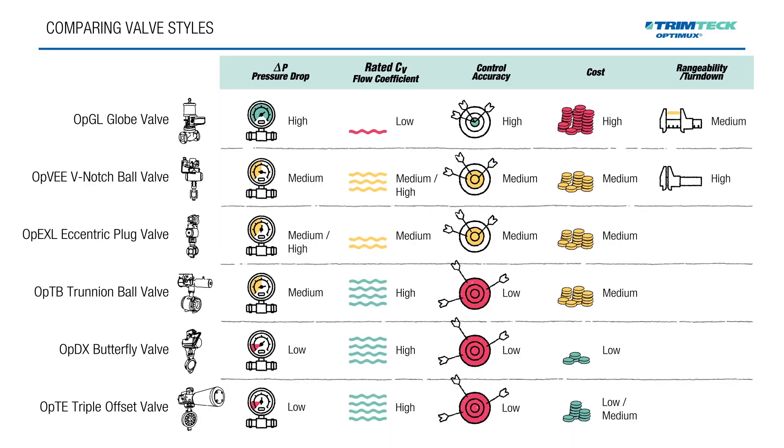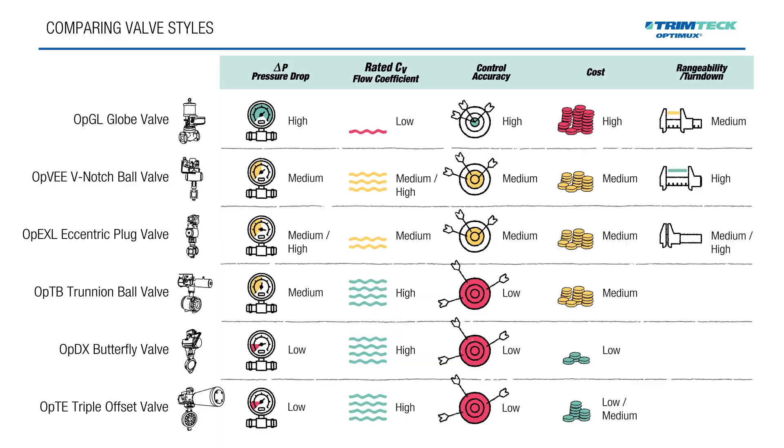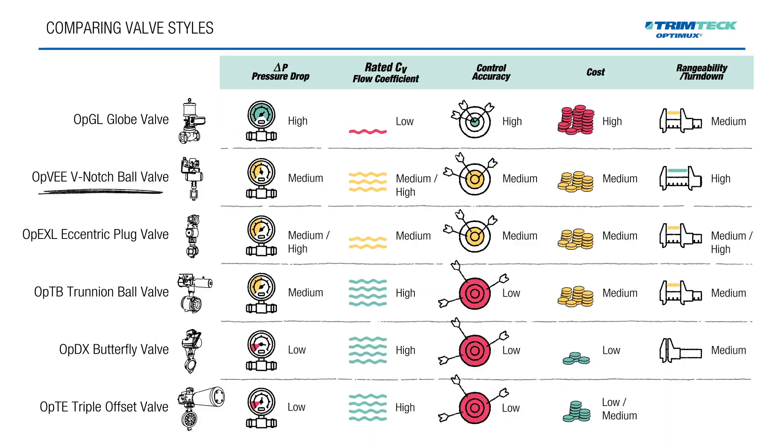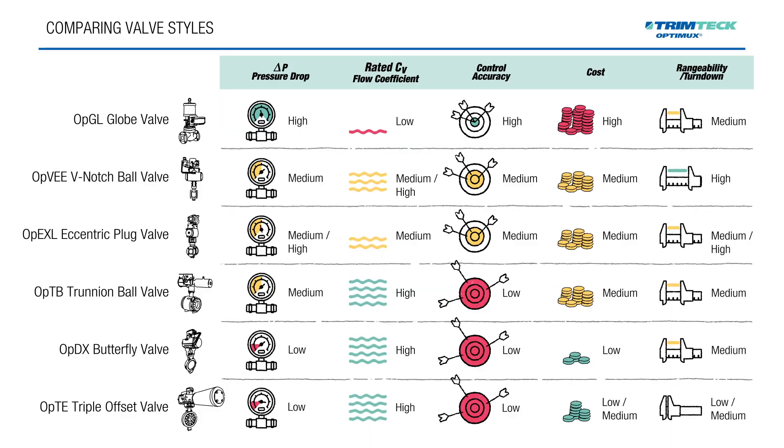Rangeability, or turndown ratio, describes how well a valve can control flow across a wide range. In this category, the V-notch or segmented ball valve leads the pack with a turndown ratio of 300 to 1. Eccentric plug valves also perform well, often delivering 100 to 1 or better. Globe valves typically offer 50 to 1, while trunnion ball and butterfly valves tend to be more limited, closer to 10 to 1 or 20 to 1.